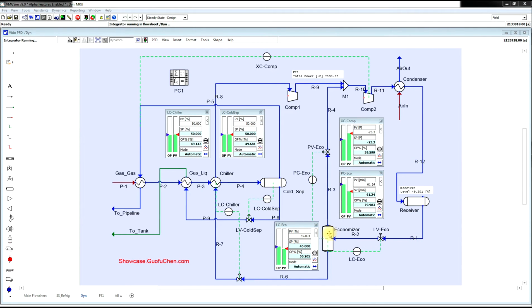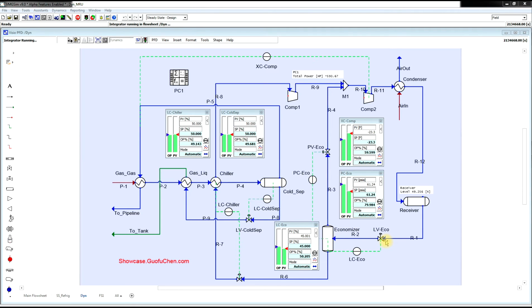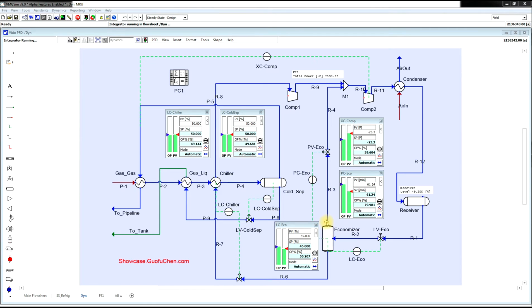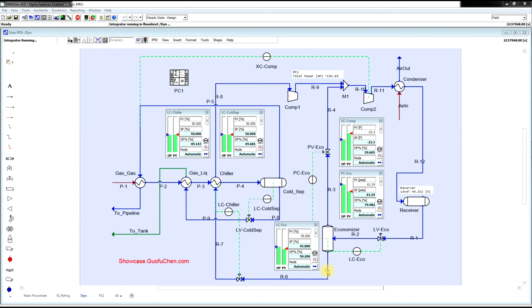Before it goes to the economizer, the liquid is throttled into vapor and liquid. The vapor portion feeds the second stage compressor, while the liquid is further throttled to feed the chiller.